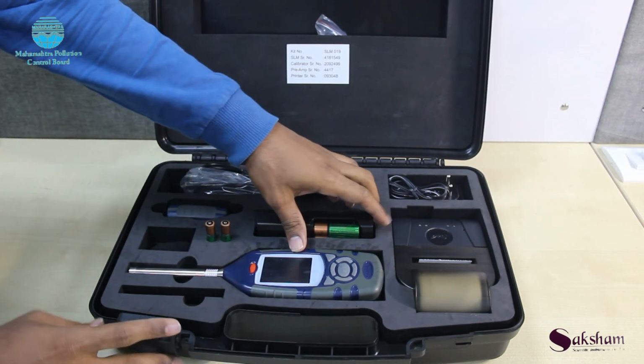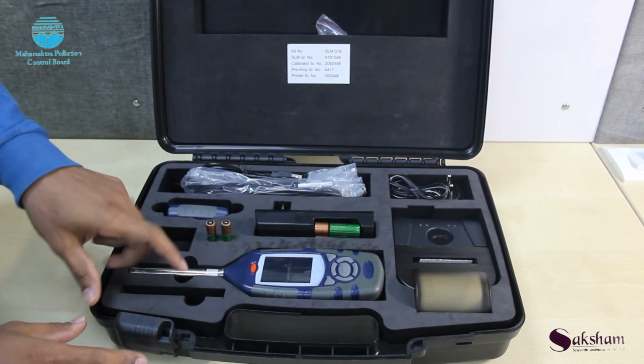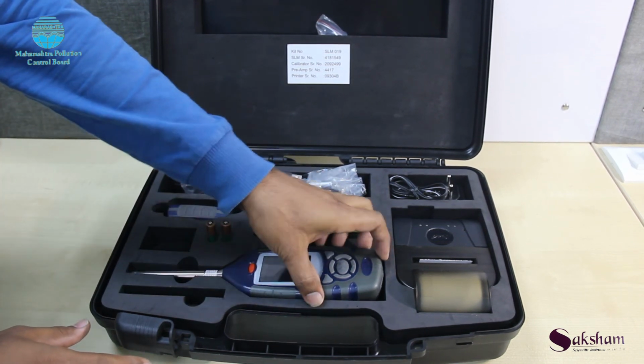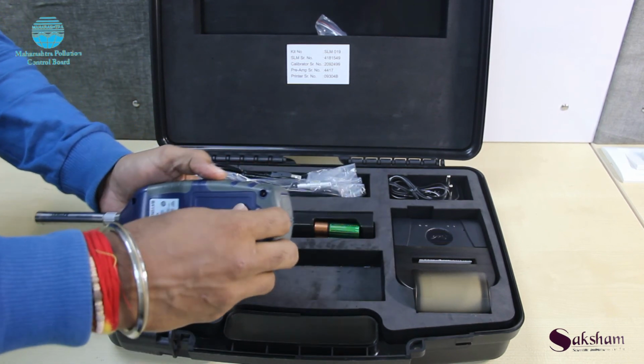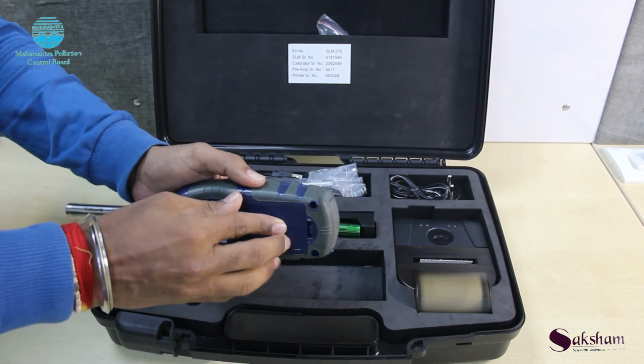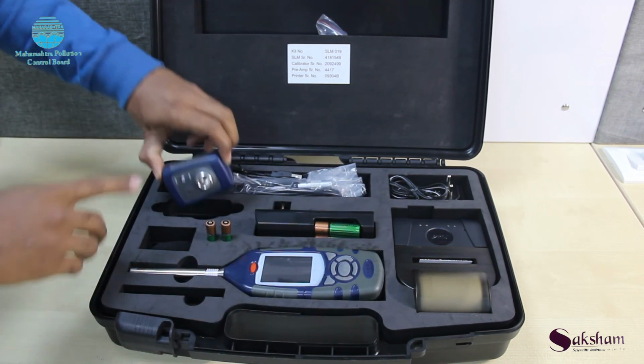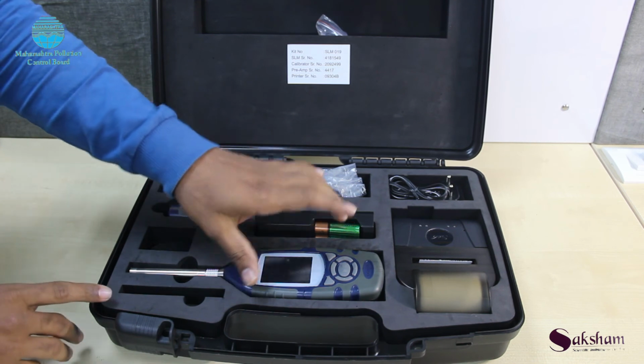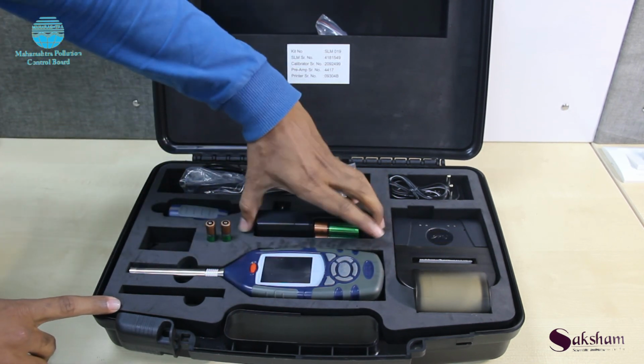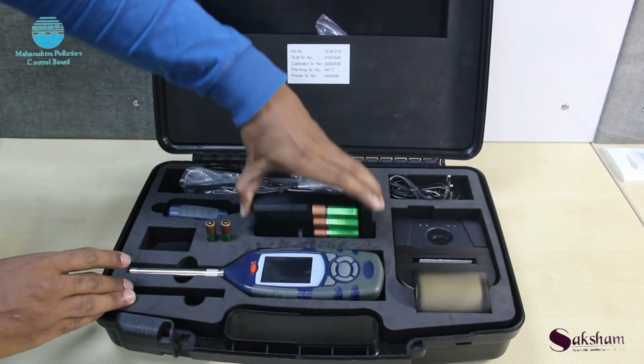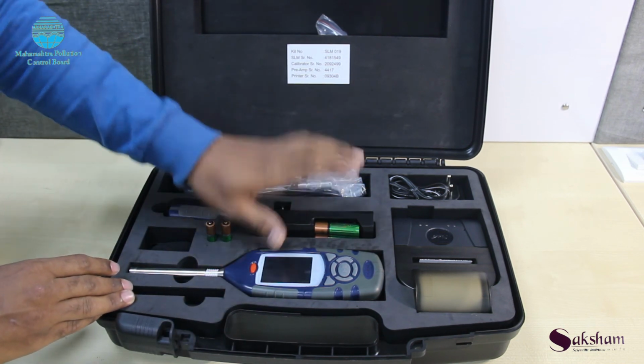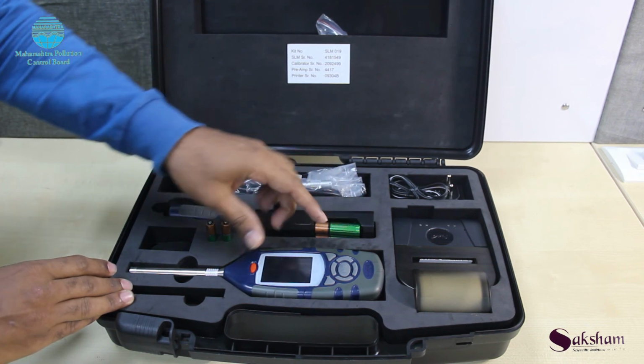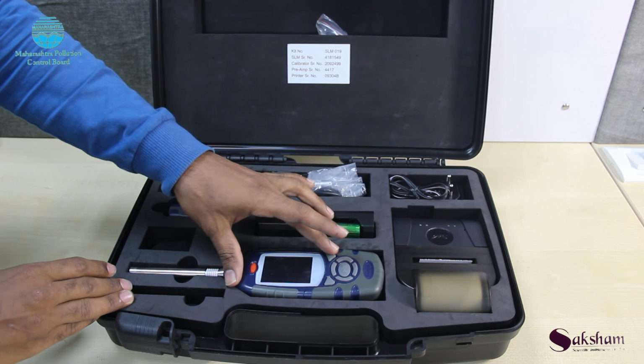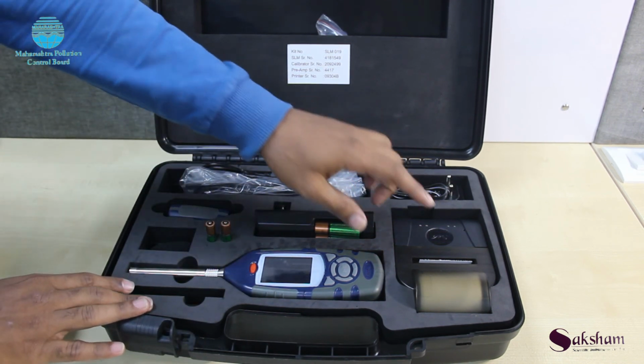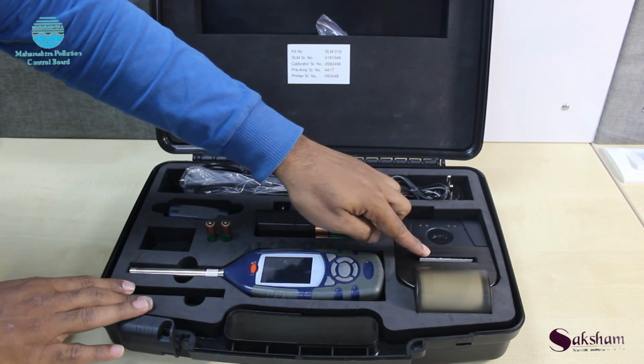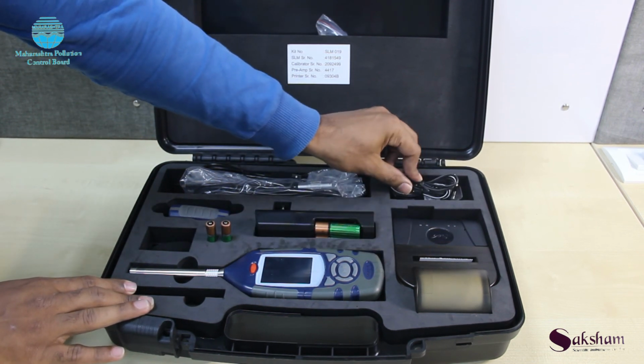You have to follow some do's and don'ts when using the sound level meter kit. When your instrument is not in use, you have to remove all the rechargeable batteries from the sound level meter as well as from the calibrator and keep them aside. Before using the kit, by using this charger, you have to charge the rechargeable batteries for at least 4 to 5 hours so that they are fully charged, and at the time of reading you have proper power backup. In the same way you have to charge your printer by using this charger adapter.